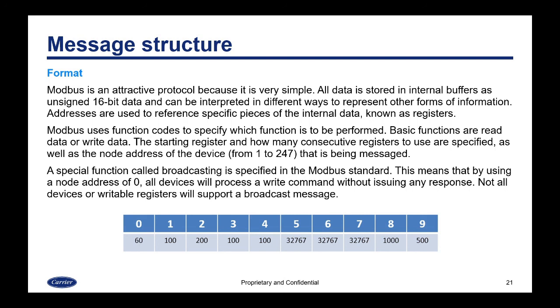Modbus uses function codes to specify which function is to be performed. Basic functions are read data and write data. The starting register and how many consecutive registers to use are specified, along with the node address of the device, which can be from 1 to 247. A special function called broadcasting is specified in the Modbus standard — by using a node address of 0, all devices will process a write command without issuing any response. Not all devices or writable registers support broadcast messaging.